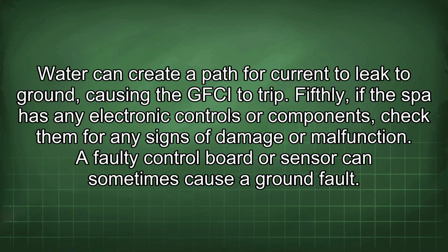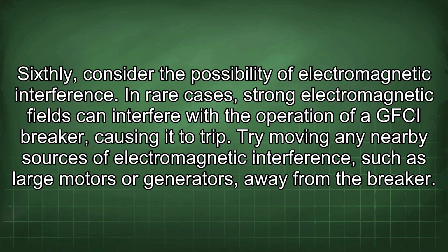Fifthly, if the spa has any electronic controls or components, check them for any signs of damage or malfunction. A faulty control board or sensor can sometimes cause a ground fault. Sixthly, consider the possibility of electromagnetic interference. In rare cases, strong electromagnetic fields can interfere with the operation of a GFCI breaker, causing it to trip. Try moving any nearby sources of electromagnetic interference, such as large motors or generators, away from the breaker.